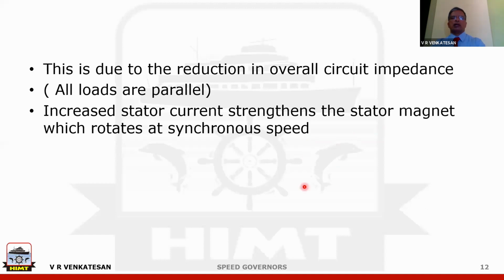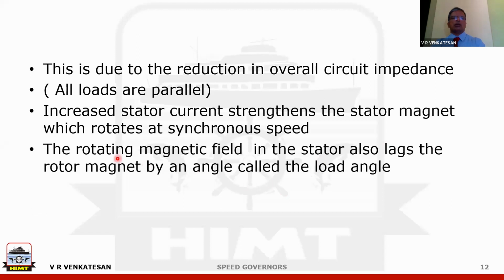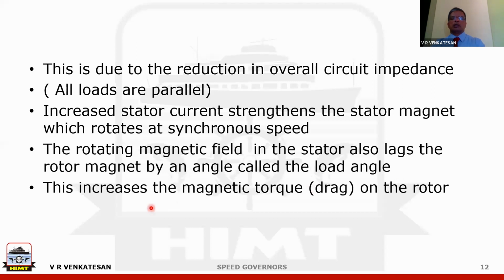Everyone understands that in an alternator, in the stator also there will be a magnet, which is a rotating magnet which rotates at synchronous speed. So the strength of this stator magnet also increases. Now this rotating magnet will lag behind the rotor magnet. The rotor magnet is what is there in the field which the engine is rotating. So the rotating magnetic field in the stator will be lagging behind the rotor magnet by an angle which is called the load angle. So what you have is the north pole and the south pole which are slightly displaced from the radial direction, and this is what will produce a torque. So this torque will oppose the rotation of the engine.